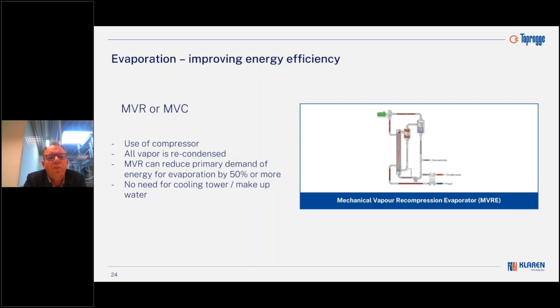Well, with mechanical vapor recompression, in fact, you use all the vapor, you increase the pressure, and by increasing the pressure, you increase the temperature, such that you can use it again as your heating medium in the heat exchanger of this evaporator. And because you condense all the vapor, there's no vapor loss stream anymore. So all the energy that you have put in the phase change is in fact recovered. And this is how you can reduce your energy compared to MEE, again, with a factor 2 or more. So that gives you a substantial saving in energy consumption.